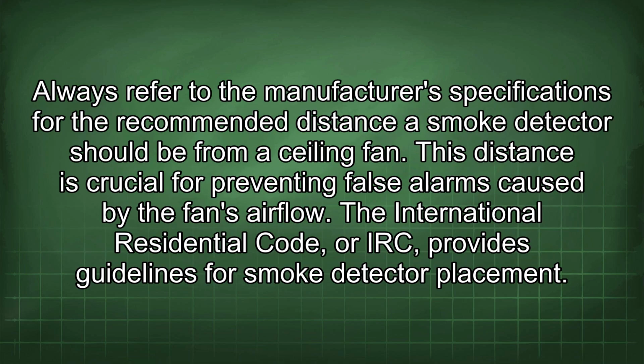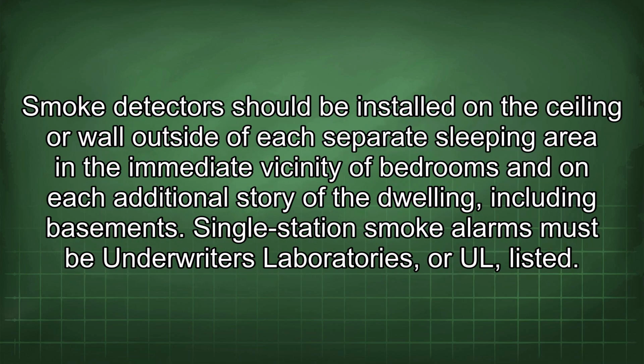Always refer to the manufacturer's specifications for the recommended distance a smoke detector should be from a ceiling fan. This distance is crucial for preventing false alarms caused by the fan's airflow. The International Residential Code, or IRC, provides guidelines for smoke detector placement. Smoke detectors should be installed on the ceiling or wall outside of each separate sleeping area in the immediate vicinity of bedrooms and on each additional story of the dwelling, including basements.